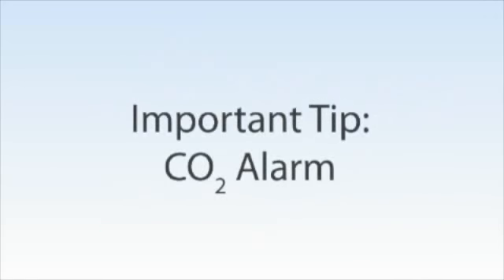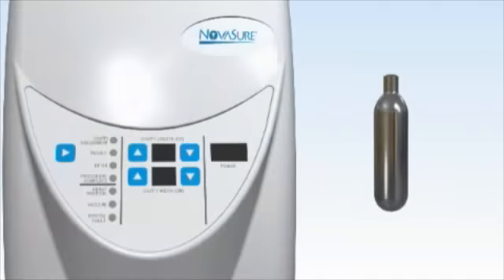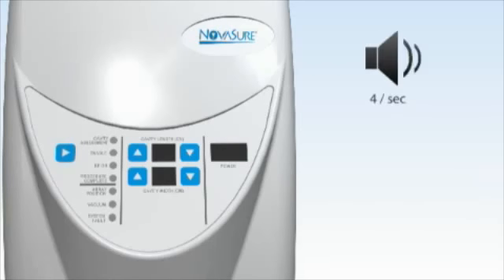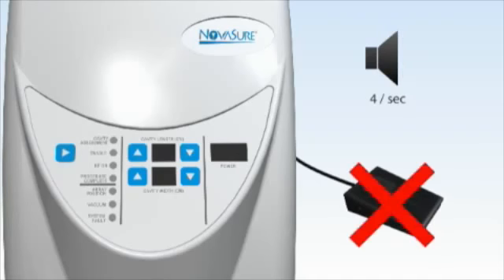An important tip regarding the audible CO2 alarm. If at any point in time when the NovaSure RF controller is on and the CO2 regulator is not on, or the CO2 canister is empty, the NovaSure RF controller will generate an audible alarm at a rate of 4 times per second. Depressing the foot switch will not turn off the audible alarm.